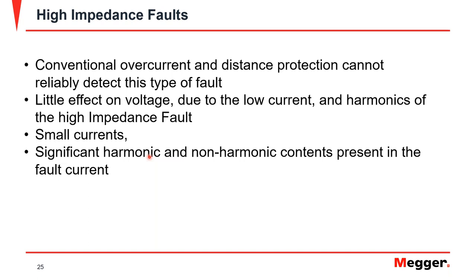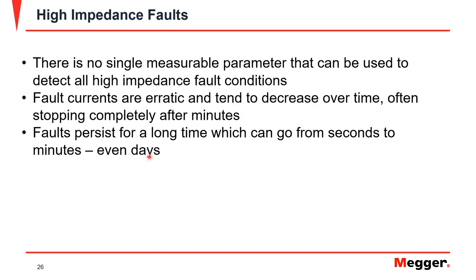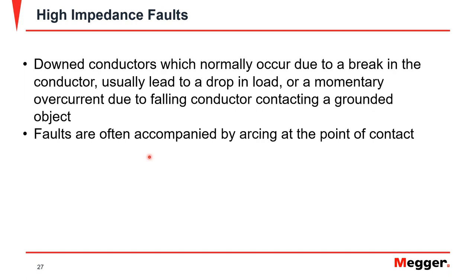High impedance faults are very difficult for conventional overcurrent and distance protection to detect. There is little effect on voltage due to the low current, so voltage cannot be relied upon for detection. The currents are small and contain significant harmonic content, which is sometimes used to detect these faults. There is no single measurable parameter that can detect all types of high impedance fault conditions. Fault currents are erratic and can decrease over time, sometimes stopping completely, yet the fault may persist for seconds or even days.